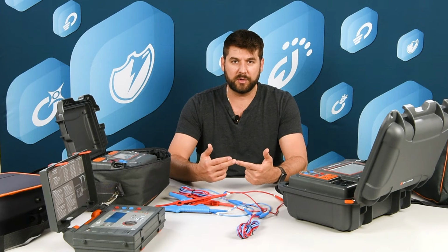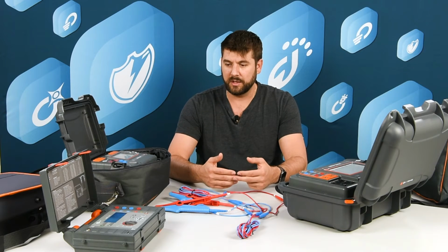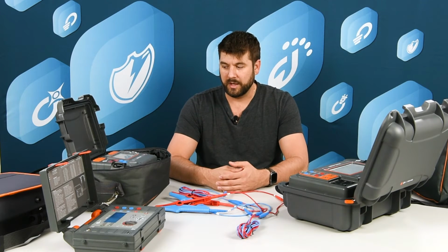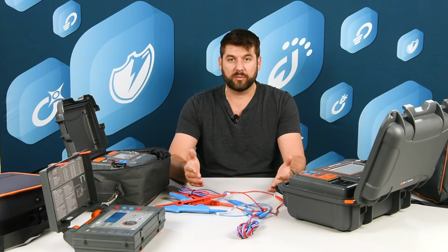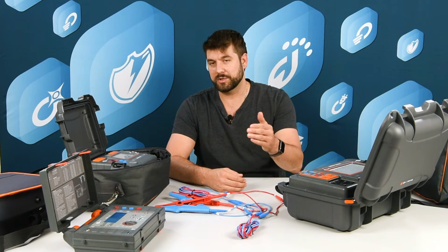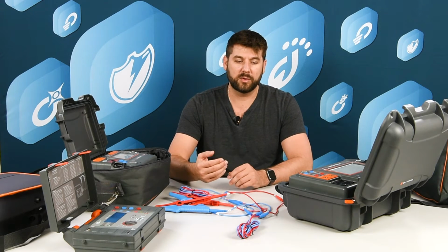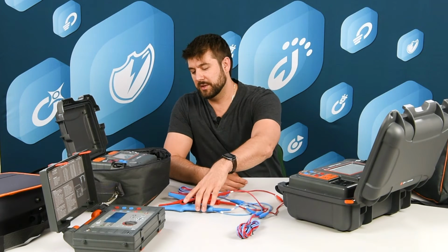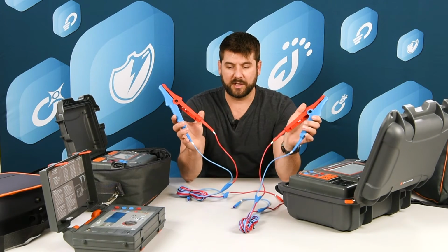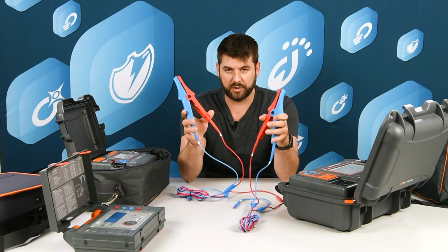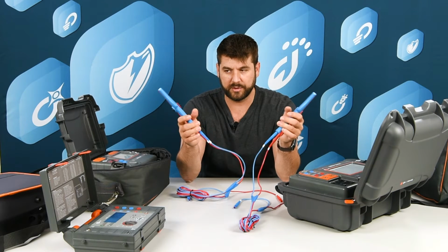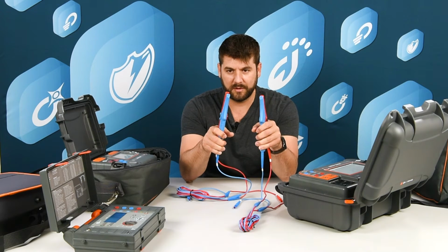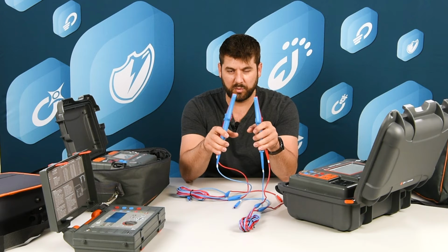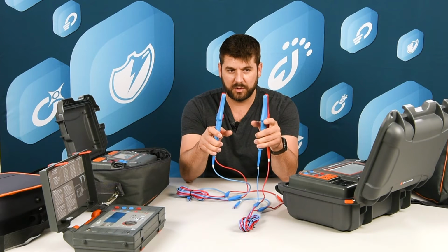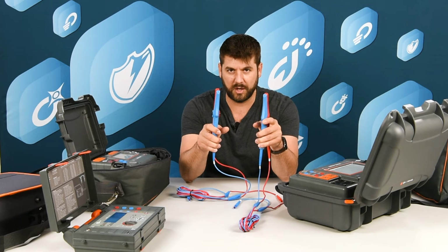So fundamentally, to measure resistance, you have to know the current and you have to know the voltage. And a microohmmeter has a current that is output from the instrument, and you will select how much current you want to push through, and then you're going to measure the voltage. So you see on these leads here, each lead has two channels, the red for pushing the current and the blue for measuring the voltage. So wherever you put the probes, it is going to measure the resistance between the two points, because the blue channel is measuring the voltage drop.